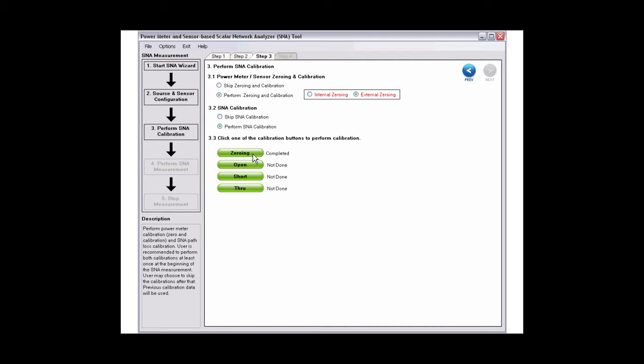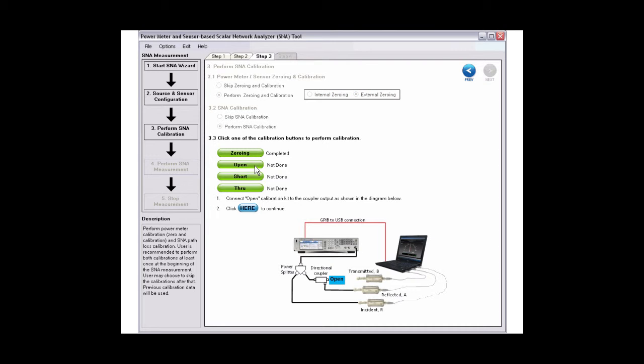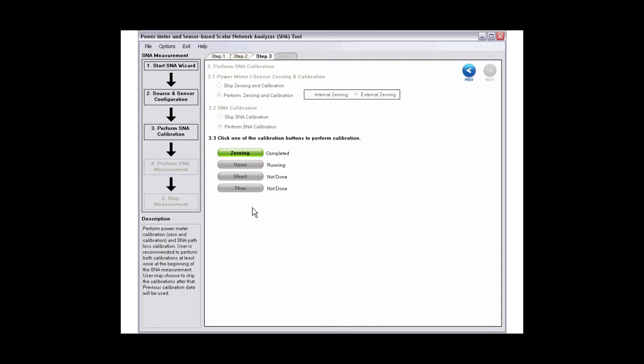For gain and return loss measurement, you will need to perform open, short, and through calibration. Click open, then connect the calibration kit accordingly. Click the button in step 2 to start calibration.